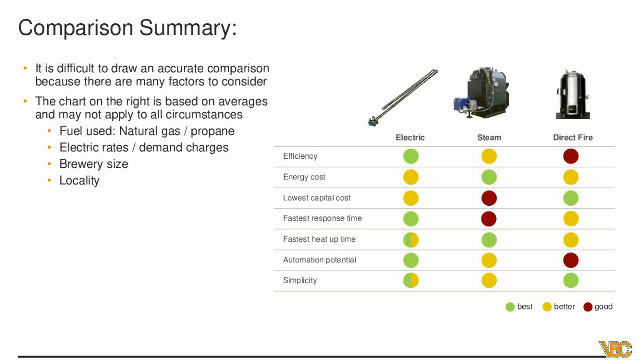Fast response time: electric has a very quick response — as soon as you turn off electric, especially with boil overs, you get an immediate response, and your boil over just sinks right down. Direct fire is number two for response — you can shut off your flame immediately, but then you're looking at residual heat in the steel that still has to transfer into the liquid. Steam is number three because not only do you have that steel heat, but you also have to cool down the condensing steam transferring phases inside the jacket — so the response time there is going to be slower.